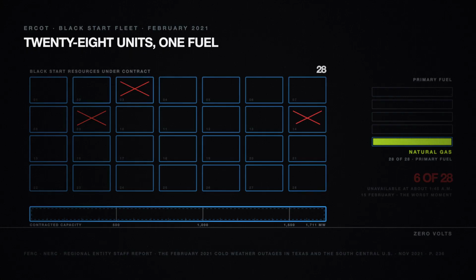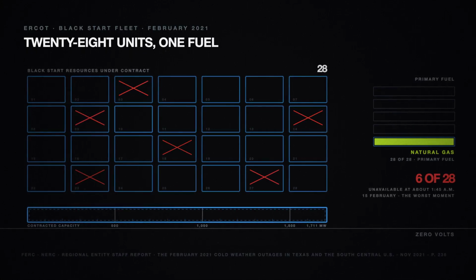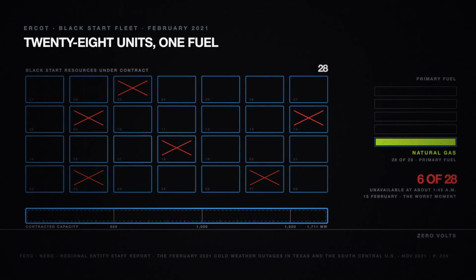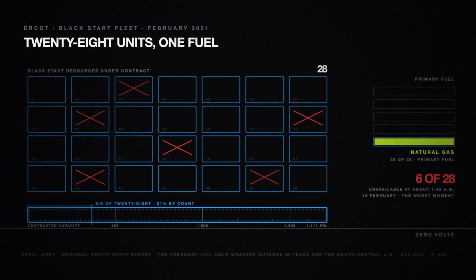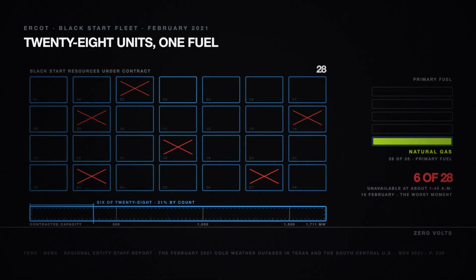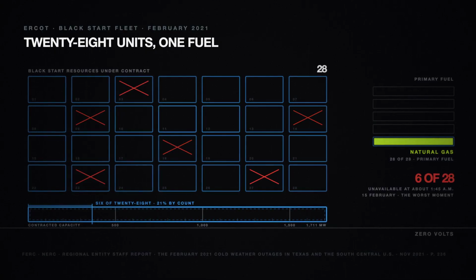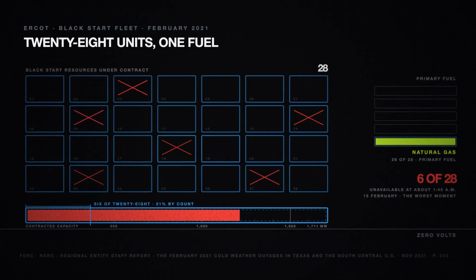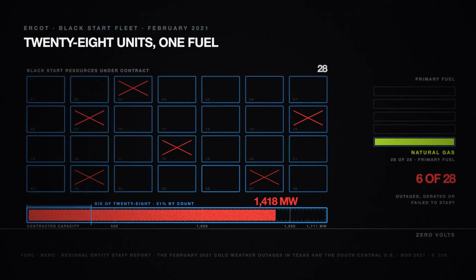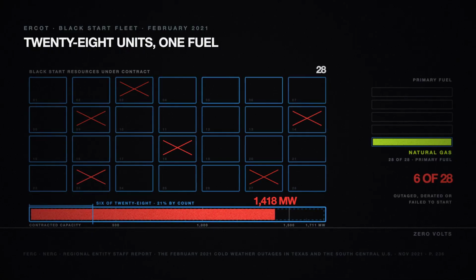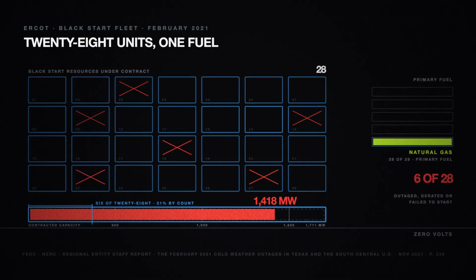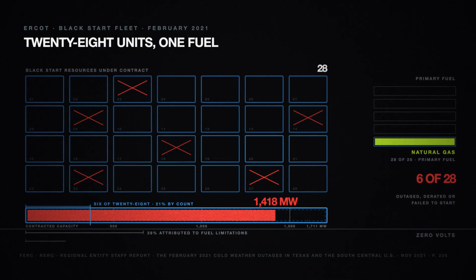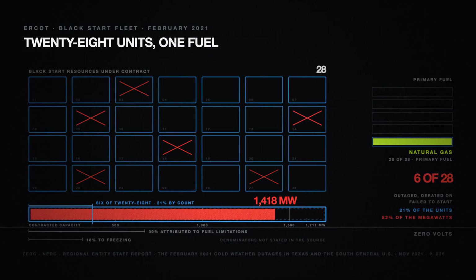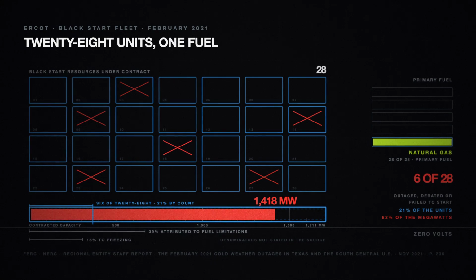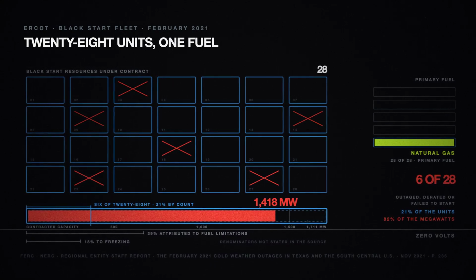At about 1:45 on the morning of the 15th, the worst moment of the event, 6 were unavailable. 6 out of 28 sound survivable. Measure the same fleet by capacity across the whole event, and it reads differently. 82% of that black start capacity, 1,418 megawatts of 1,711, suffered an outage, a derate, or a failure to start. 39% are attributed to fuel limitations, 18% to freezing. One fleet measured 2 ways, 6 units out of 28, 82% of the megawatts. The federal reviewers wrote the conclusion themselves.